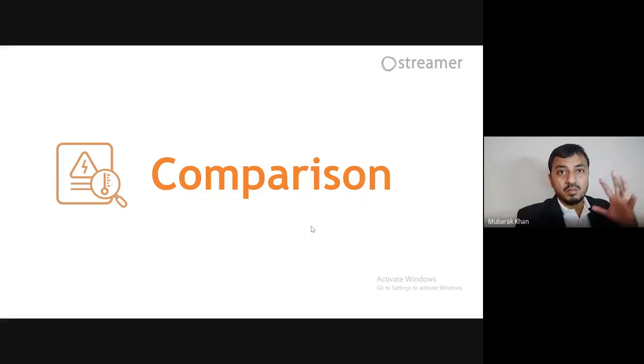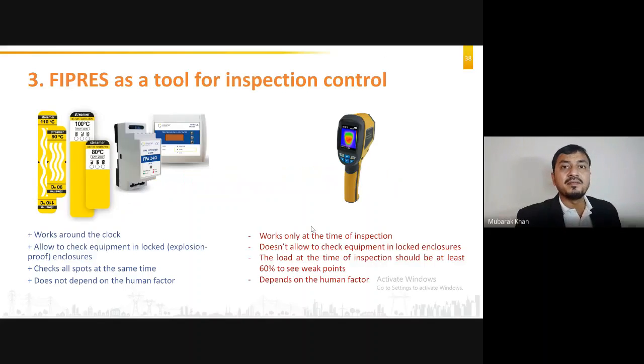Now let us compare with other methods available. First, thermography - the most common method of monitoring overheating of electrical joints. But the issue is thermography works only at the time of inspection. Like when I am doing the thermography, at that moment if the temperature of the joint is high, it will be detected, otherwise it will not be detected. We saw from so much discussion that the temperature of the joint can become high at any point throughout history because of overloads, etc. So it works only at the time of inspection. FIPRES works round the clock.